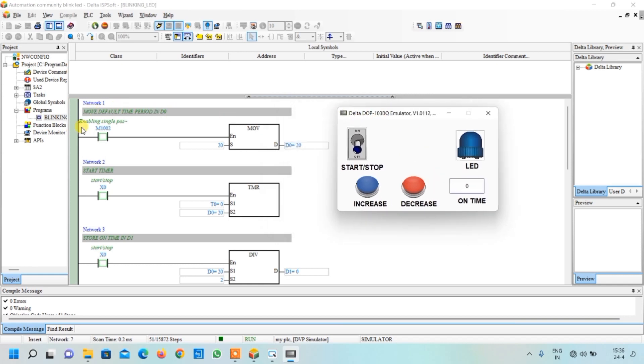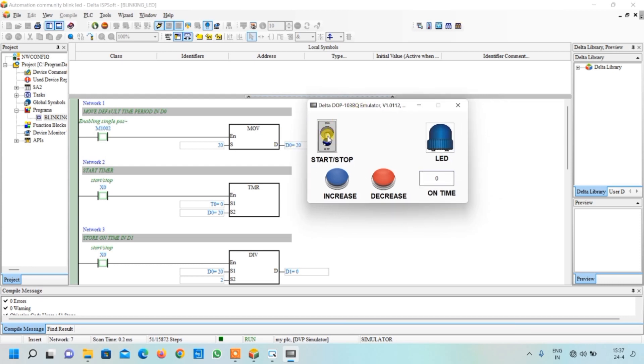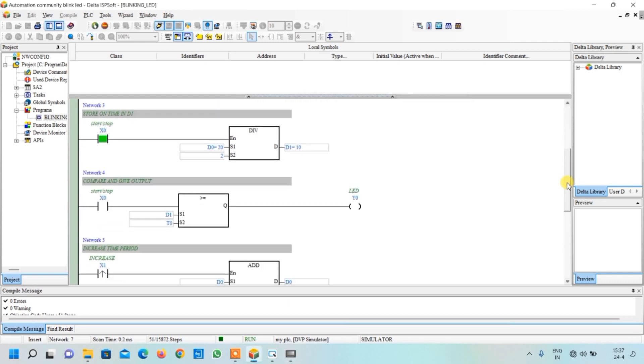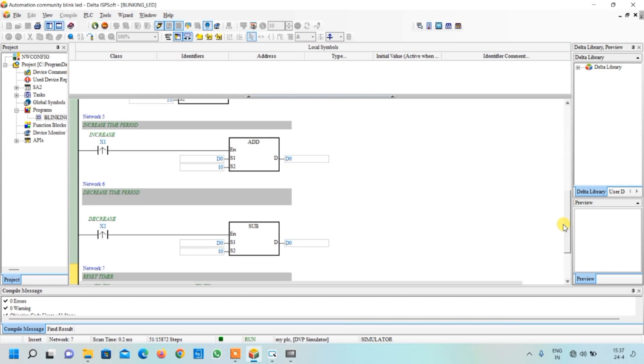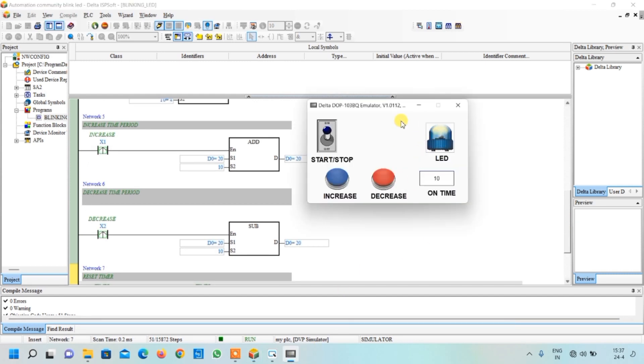The PLC is in run mode and the default time period has already been moved to data register D0. When we turn it on, the LED starts blinking. As you can see, it is blinking with a time period of two seconds - on for one second and off for one second.